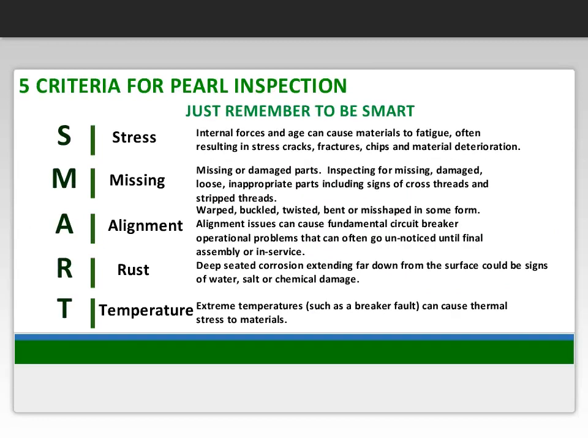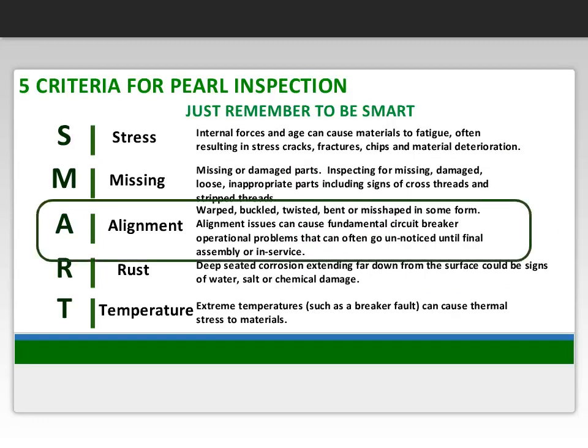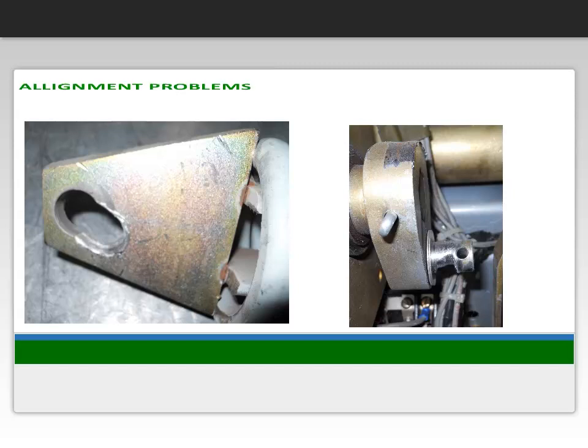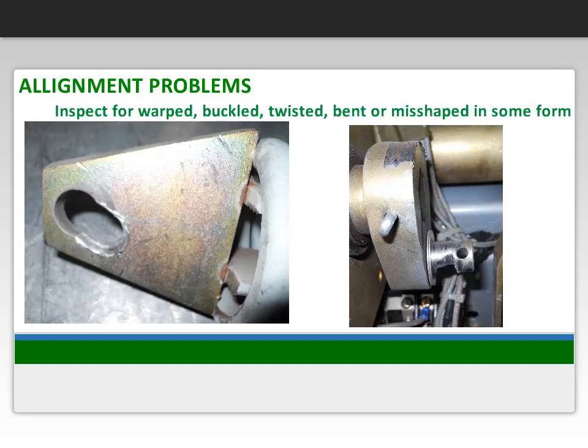The next point in the inspection process involves A for alignment. Warped, buckled, twisted, bent, or misshaped in some form, alignment issues can cause fundamental circuit breaker operation problems that can often go unnoticed until final assembly or when the breaker is in service. With alignment issues, you're looking for warped, buckled, twisted, bent, or misshaped parts in some form. Typically, you will be looking for this on metal frames, mechanism assemblies, and contact assemblies.